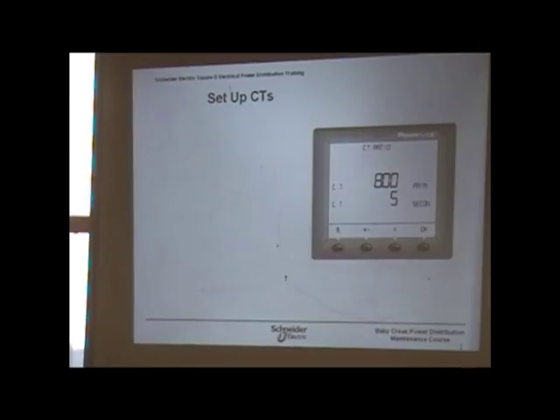And you've got voltages, but there's no amperages. Like I said, what's going on? Go in there and check to see if the CTs have been set up. And it's real easy because you go into the setup menu, you do the zeros, then you go to CTs. When you hit CT, it's going to show you the CT primary. And then you'll scroll up or down, and this little arrow is going to be up or down. One of these two will make it count.